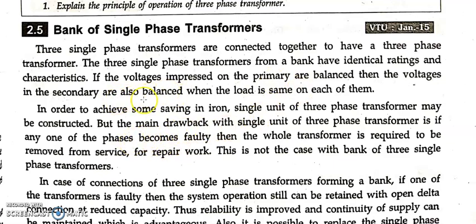The characteristics are all the same, but we saw the advantage of having a single 3 phase transformer. In order to achieve some economy, a single unit 3 phase transformer may be constructed, like I told you. The main drawback of the single unit 3 phase transformer is that if any one phase has a problem, for example if a phase gets burned, then you can't use that single 3 phase unit. The whole unit has to be removed, and that particular phase has to be replaced. This is the disadvantage of a single 3 phase transformer, and it takes a lot of time.